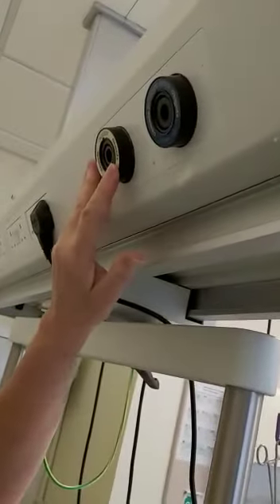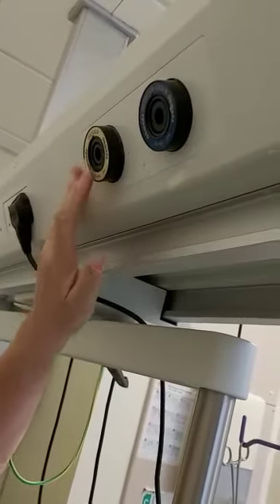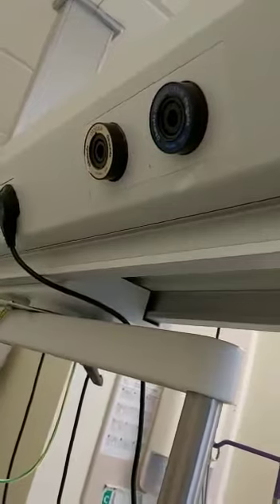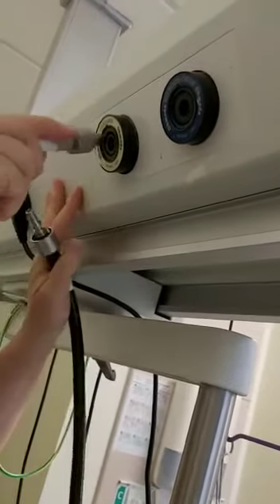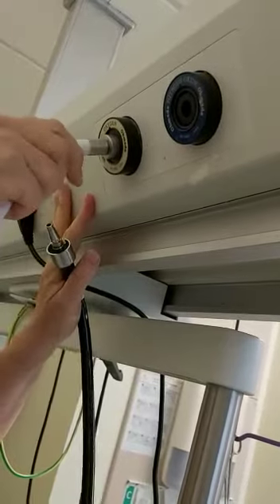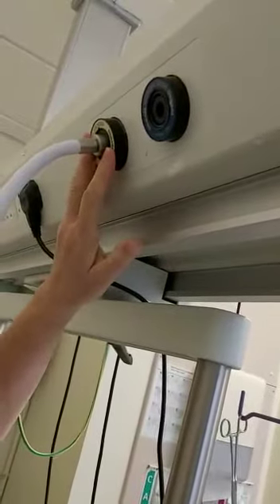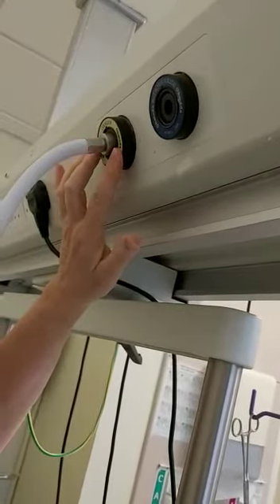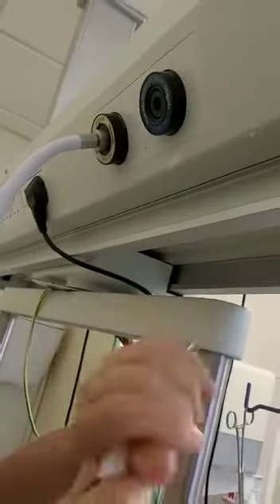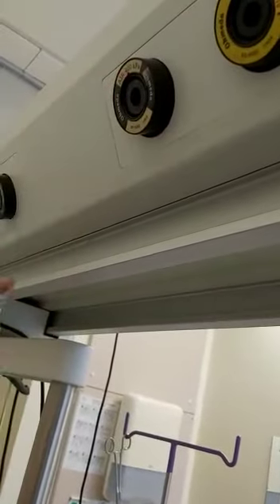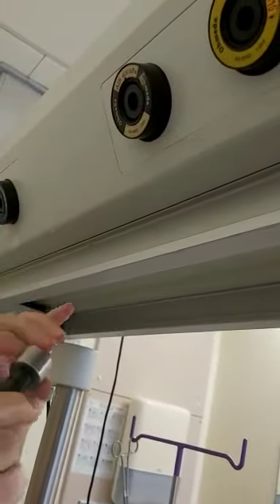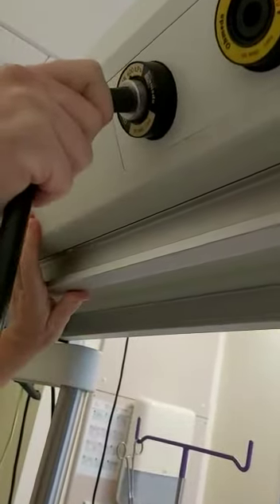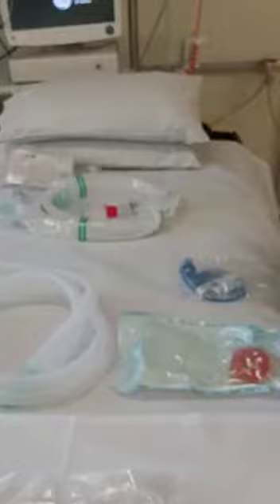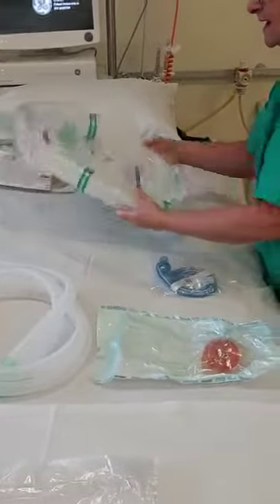So as you can see here, this is your oxygen supply. It's white around the outer rim. It does actually say oxygen at the top, and you're going to have your notch to the top, push it in quite firmly, and then just give it a slight tug to make sure that it is actually in place properly. Don't ever stand in front of these, because if you haven't inserted it properly, they can pop out and obviously hit you. And then over here we've got our air supply, which is black and white, and again says air at the top, and you've got a little notch here that you line up at the top, push in to engage it properly.